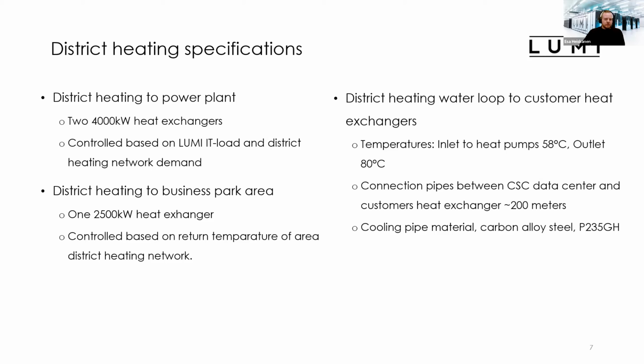So we are running 80 degrees outlet from the heat pumps, and it's returning at approximately 58 degrees Celsius back to the heat pumps. And the connection pipe between our data center and the customer's heat exchangers is approximately 200 meters. So those are pretty close to utilize the waste heat from the Lumi. And these cooling pipes are done.